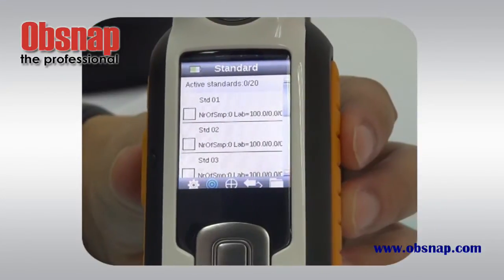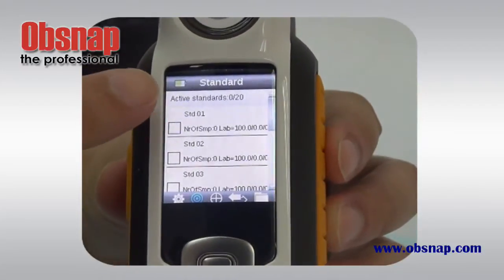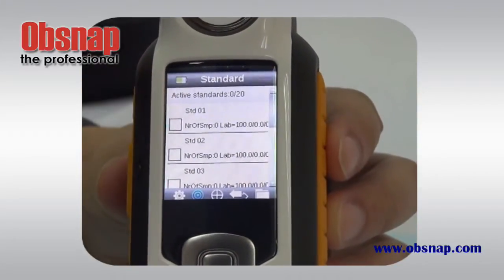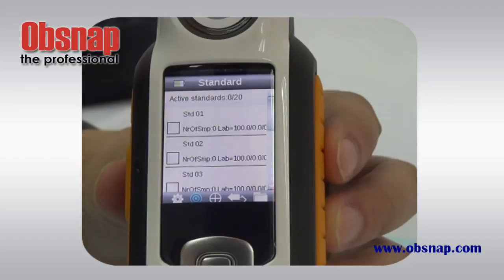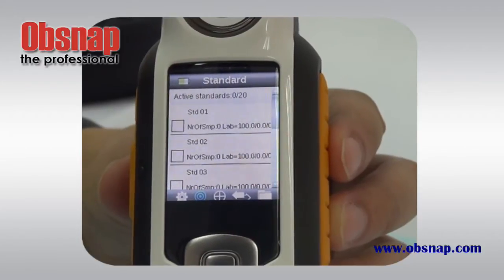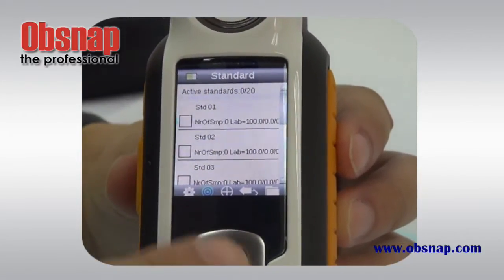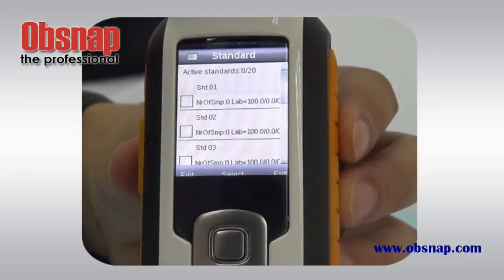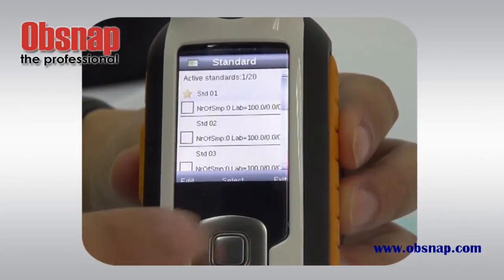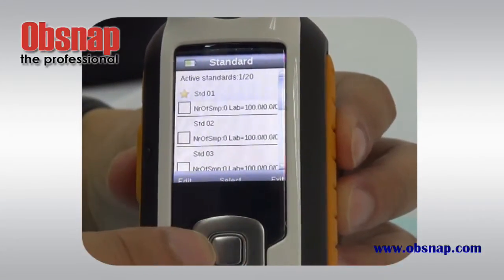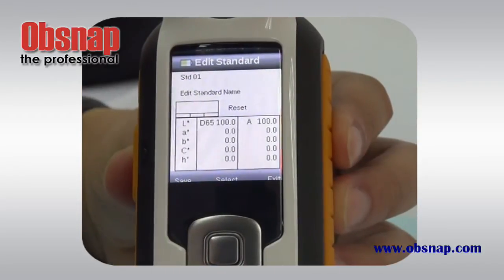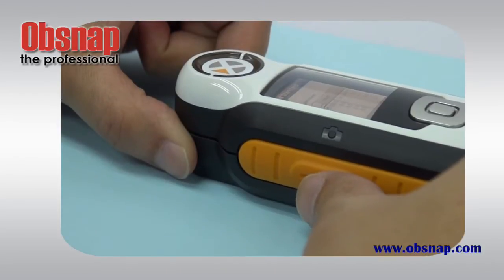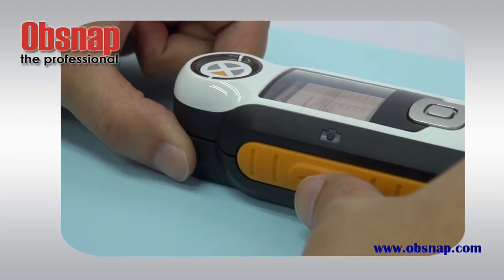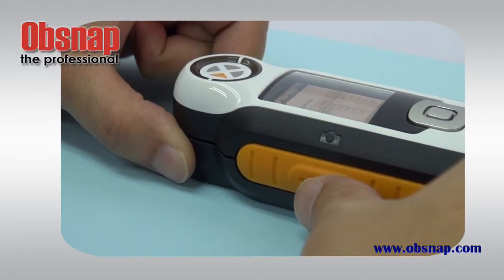This RM200QC is able to store 20 standards. To measure the standard and save it into the RM200QC, at first, we come to standard number one, we select it, and then we press the edit button, and we can start measurements. Because we already set the measurement setup to 3 averaging to measure the standard, we need to measure 3 times when we set the standard.